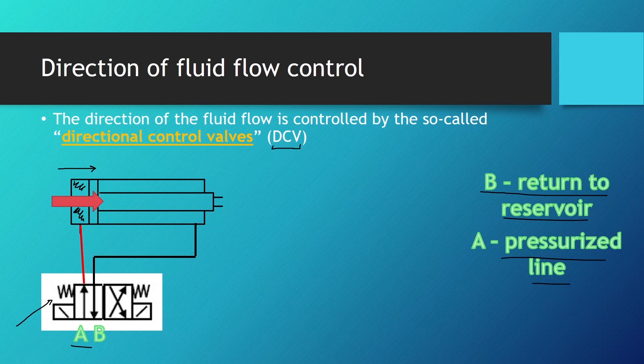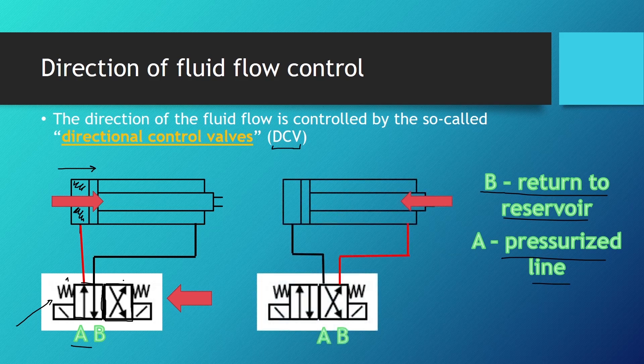Now, what happens if we push this directional control valve to the left side, changing from position one to position two? The pressurized fluid now goes to the back of the piston, pushing the piston and piston rod to the left side — in other words, retracting the cylinder. The other side fluid goes back to the tank through line B. This is why the direction of fluid flow directly influences the direction of the force exerted, or torque if we're talking about rotational hydraulic motors.